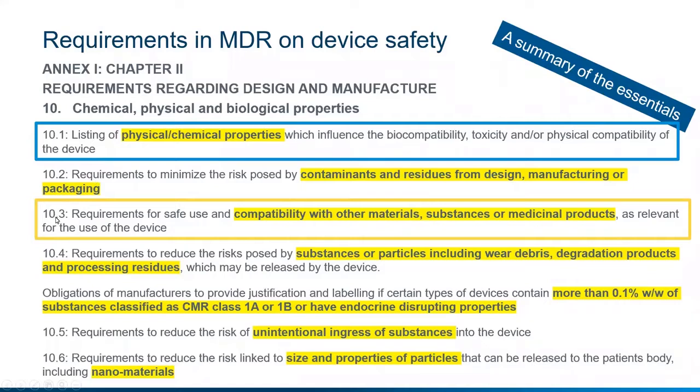In section 10.3, the requirements for safe use and compatibility with other materials and substances or medicinal products are listed. And here, obviously, the compatibility with the medicinal products where you use the device is the key point that you need to test and document, that your device is suitable for delivering the kind of medicinal product that you are intending to use it for.